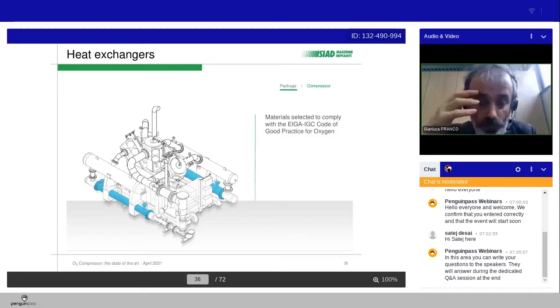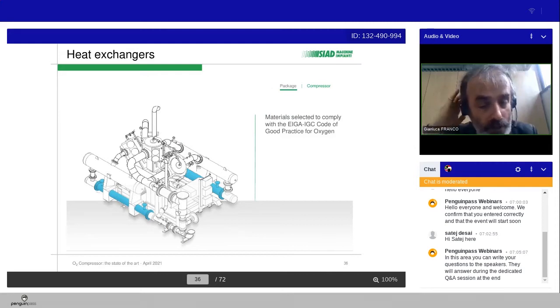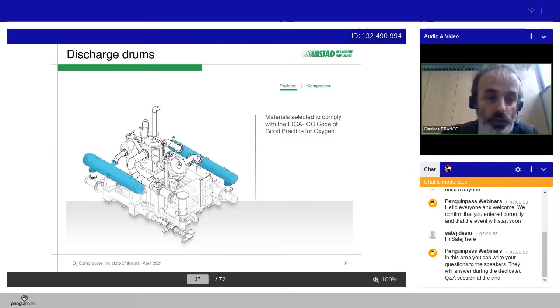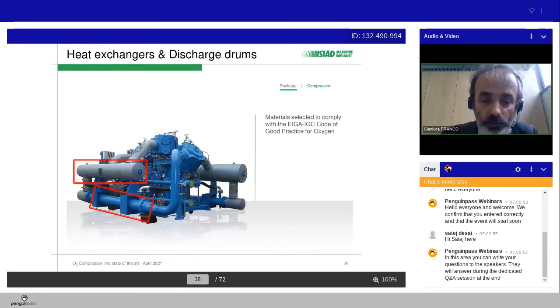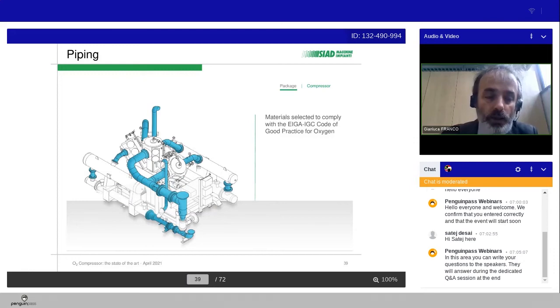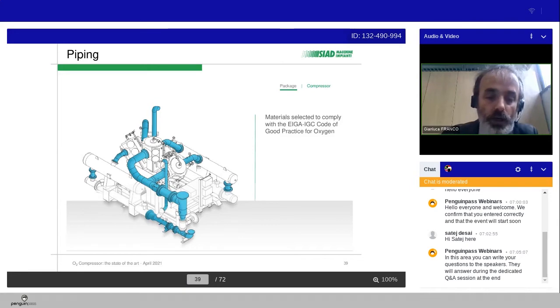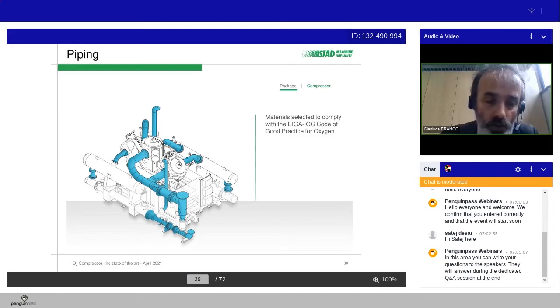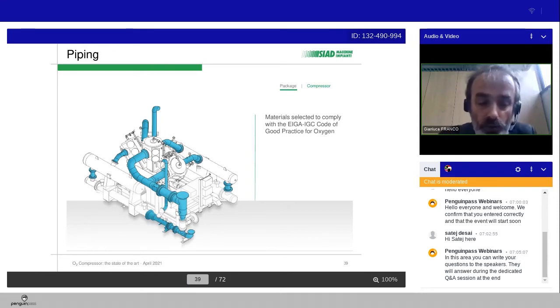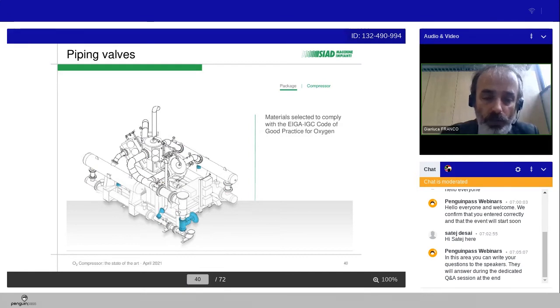Of course, for the compressor and the complete package, the material selected must comply with the EIGA-IGC code for good practice for oxygen, so for the heat exchanger and for the drums, but even for the piping. So all the package must follow the international rules for safety and good criteria of the design for oxygen application. It means, for example, for the piping that when you calculate the piping, there is a chart of maximum velocity admissible according to the operating pressure, in order to avoid the auto-ignition process due to the percentage of oxygen to be compressed.